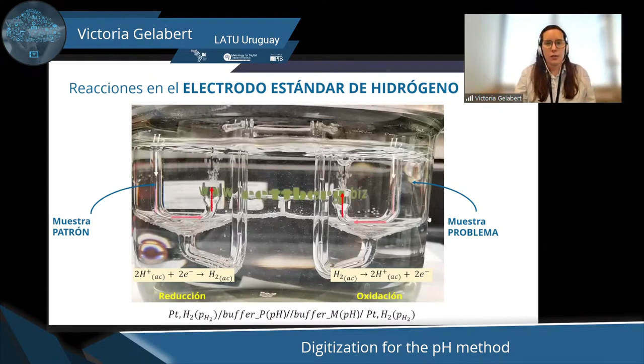So what I need here is a software which is permanently measuring this throughout the whole reaction. Now, balance is extremely, sometimes it's theoretical. So what I establish is conditions. I say, okay, after a certain period of time, for example, here it's going to be 30 minutes, the potential difference when the balance is found should not be superior to a certain level. And this is something I'm going to show you next. So the hydrogen is bubbling here.